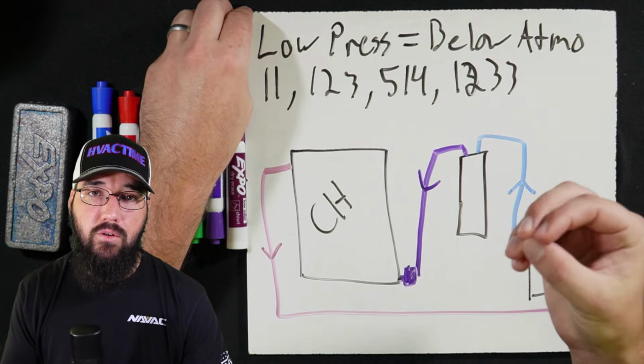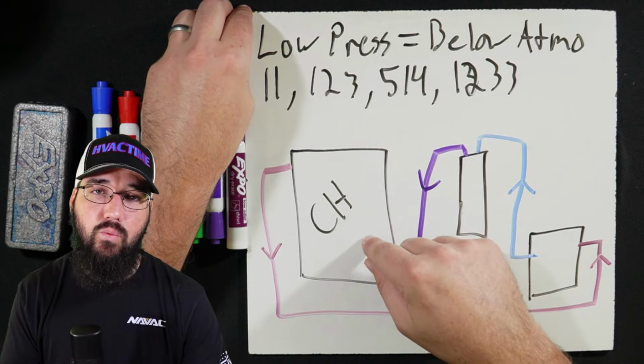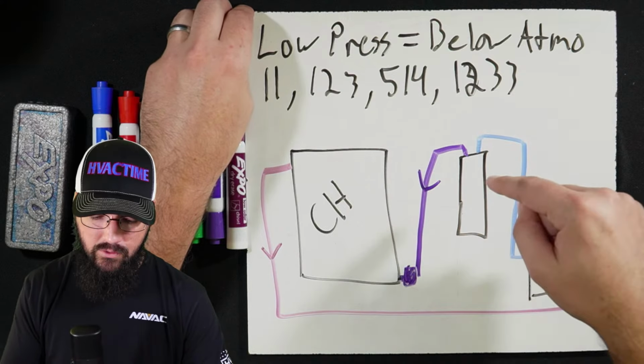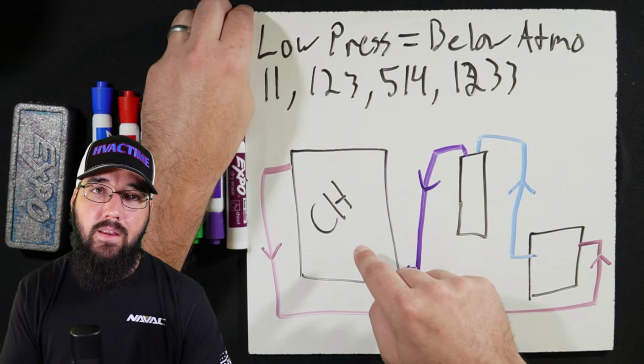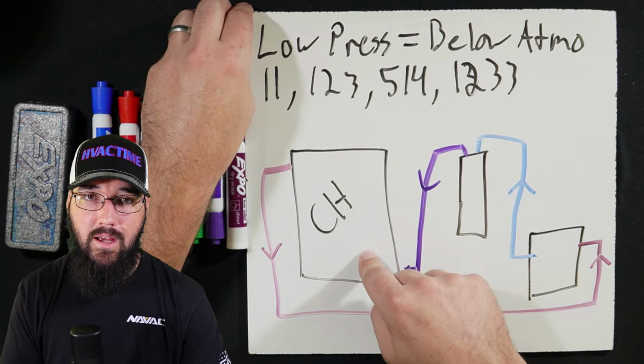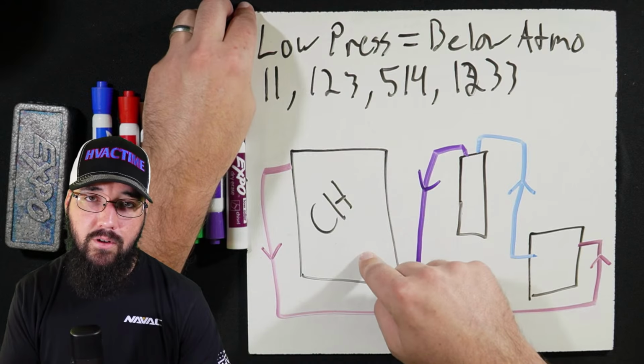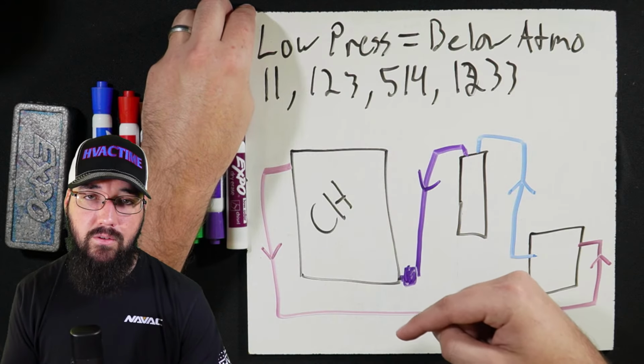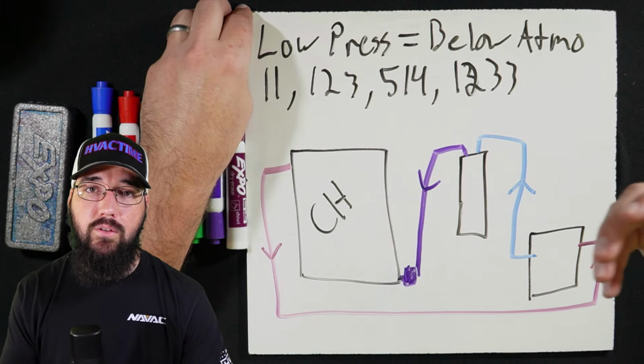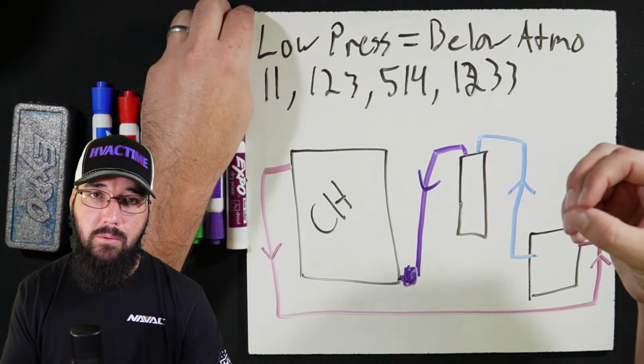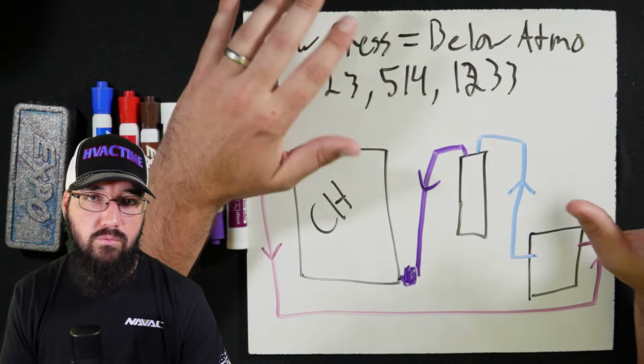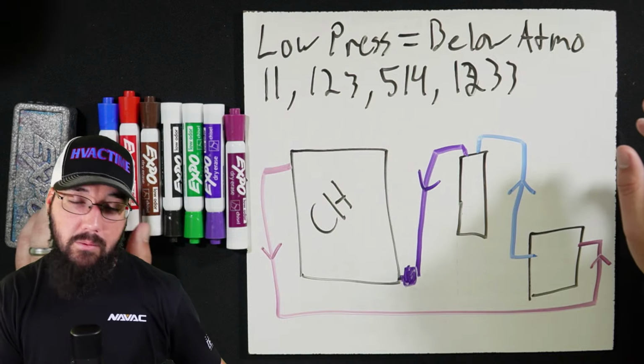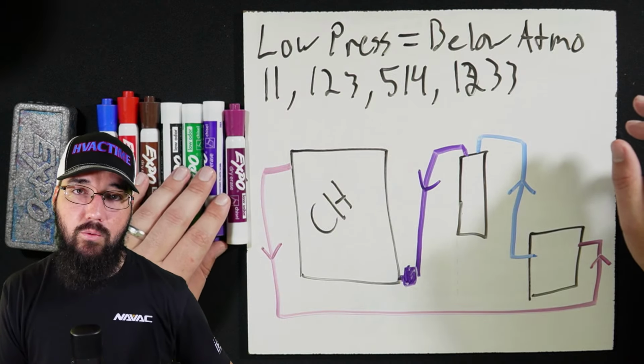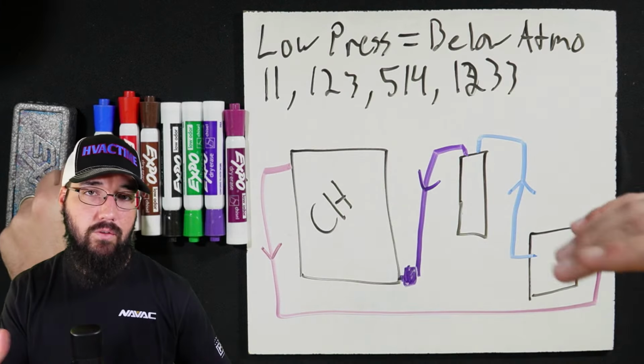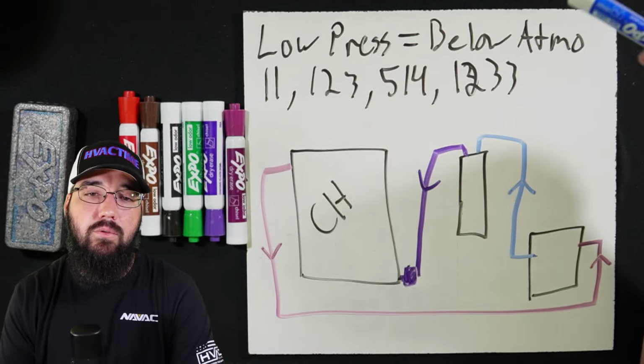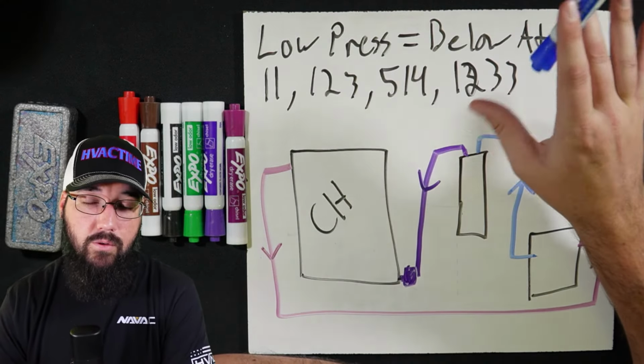refrigerant saturation is below freezing and we have liquid make contact with the tubes, which will happen in the evaporator. So as you're pumping this liquid in, you will start to have liquid make contact with the tubes in the evap. If that liquid refrigerant is below freezing temperatures, you run the risk of freezing those tubes. A frozen tube will rupture and wreck your entire day, your week, your month, probably your year, because then you're talking about a retube or at least plugging that tube. It's a mess, and then you've got to clean all the water out of the machine, out of the refrigerant. It becomes a disaster. So we don't want to do that.